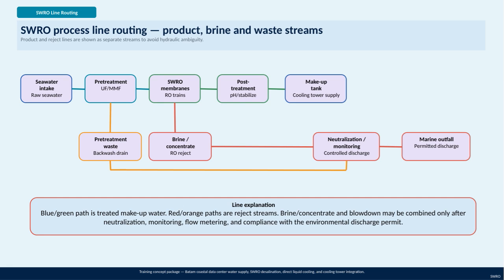This treated water is then sent to the makeup tank, which supplies the cooling tower and the Batam coastal data center's water needs. On the reject side, we have brine concentrate and RO reject streams that need careful handling. These reject streams, including backwash waste from pretreatment, undergo neutralization, monitoring, and flow metering. Only after meeting strict environmental discharge permit requirements can these combined brine and blowdown streams be safely discharged to the marine outfall. This entire line routing is designed to integrate seawater desalination with the water supply for cooling tower operations and direct liquid cooling, ensuring both operational efficiency and environmental compliance.